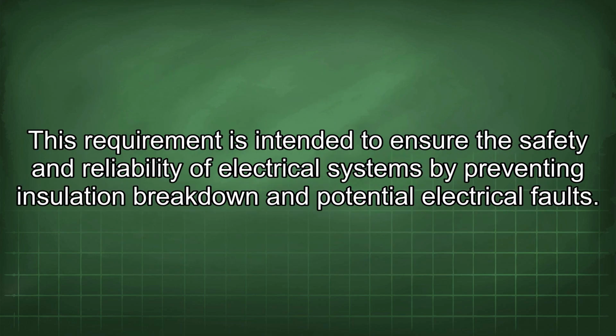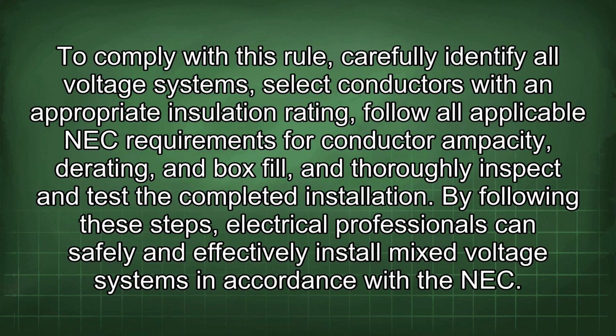This requirement is intended to ensure the safety and reliability of electrical systems by preventing insulation breakdown and potential electrical faults. To comply with this rule, carefully identify all voltage systems, select conductors with an appropriate insulation rating, follow all applicable NEC requirements for conductor ampacity, derating, and box fill, and thoroughly inspect and test the completed installation. By following these steps, electrical professionals can safely and effectively install mixed voltage systems in accordance with the NEC.